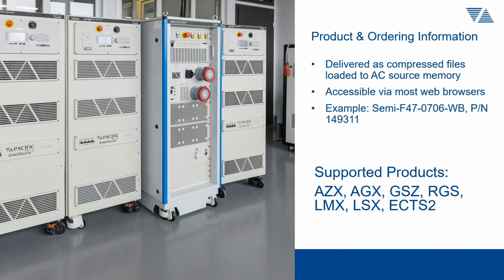By having the ability to do it in-house, we do something similar, although we don't have to comply with SEMI F47. Our equipment is not typically used for semiconductor manufacturing, but we have similar requirements for CE mark and UL compliance that we test in-house. The engineering team will do their own pre-testing in-house before they venture out to a third-party lab and start paying the daily rates to run the tests there for third-party certification. So it's a very common practice for most customers to do that in the interest of saving time and money.